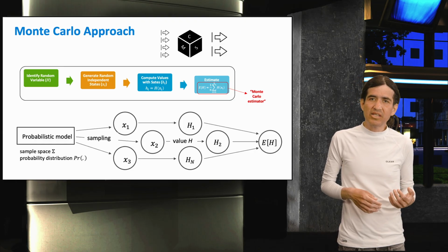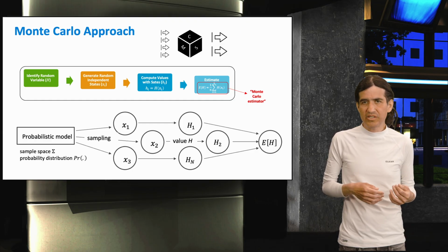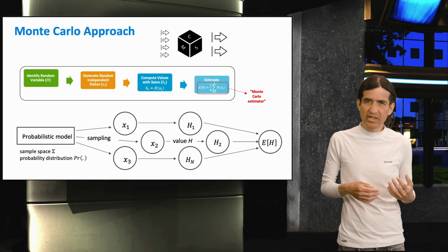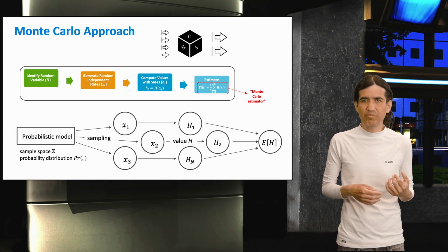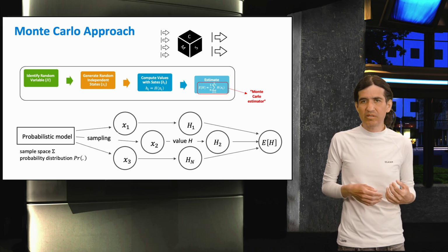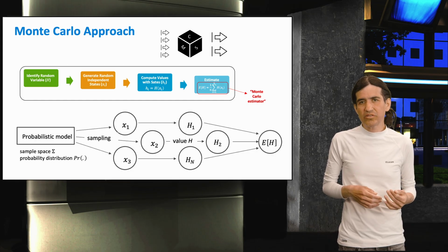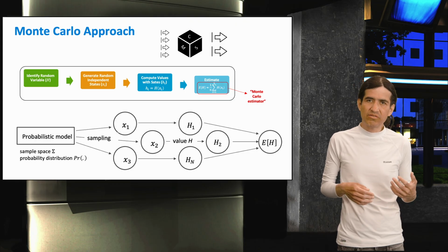The main steps of non-sequential Monte Carlo involve, first, define uncertainties and their distributions. Next, randomly generate many independent scenarios representing different possible system conditions. Next, run a deterministic power flow for each scenario. Finally, combine results to compute probabilistic statistics like expected values, variances, or risk metrics.